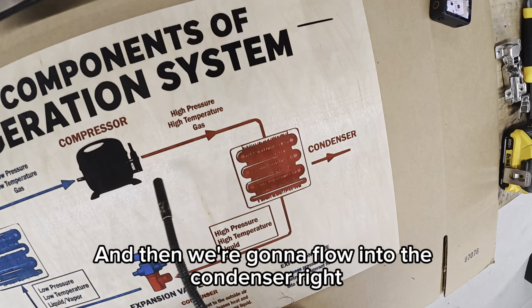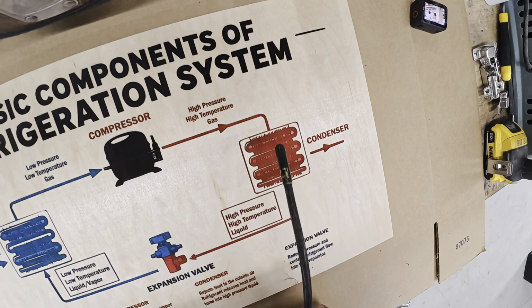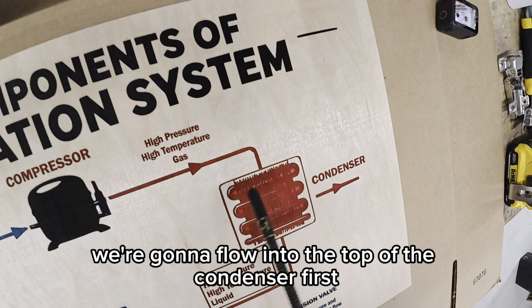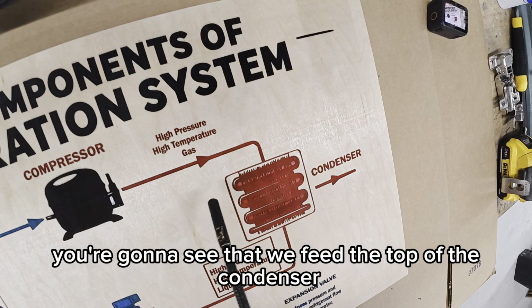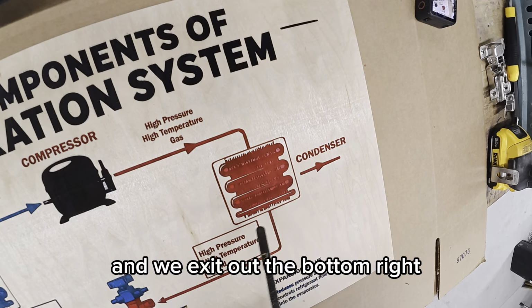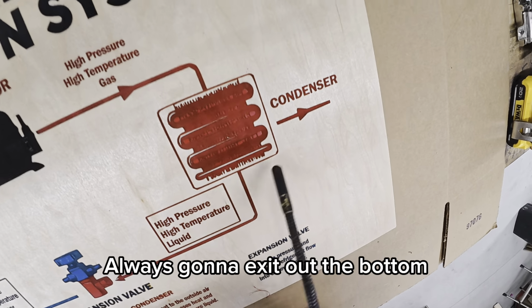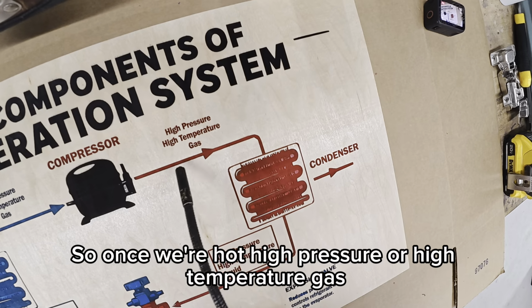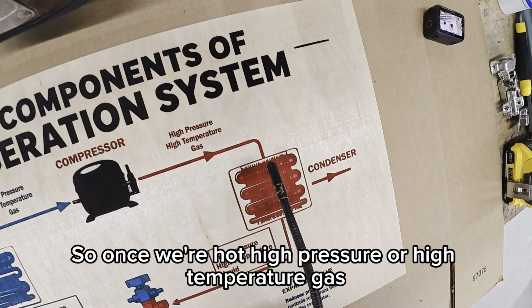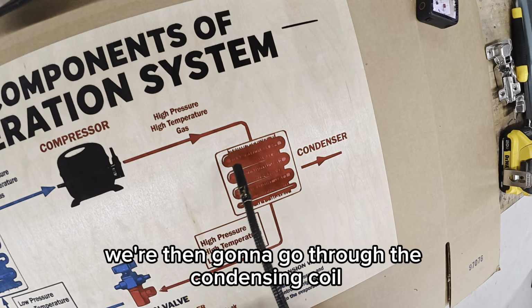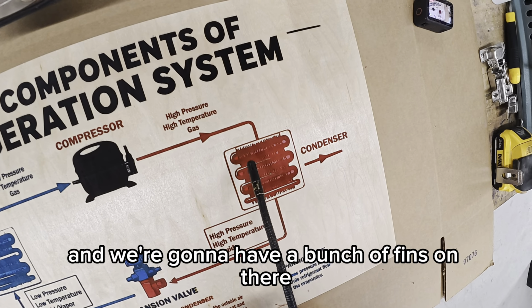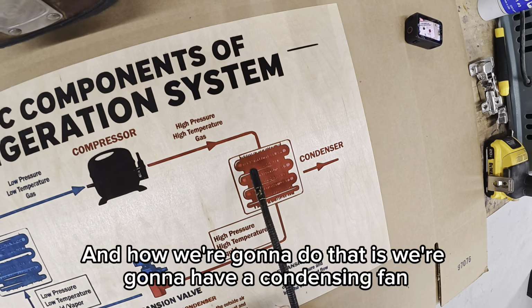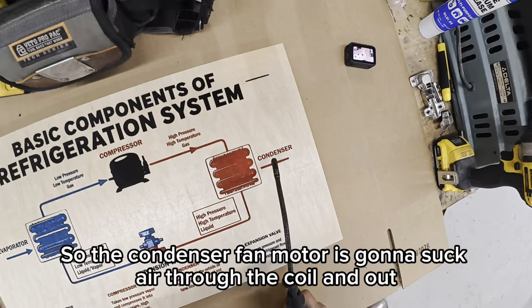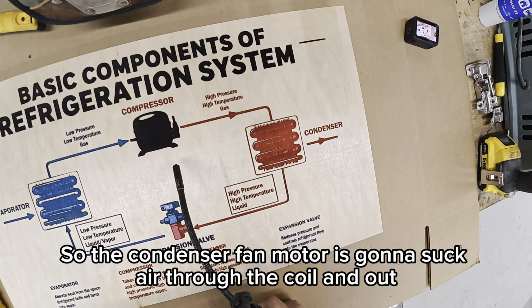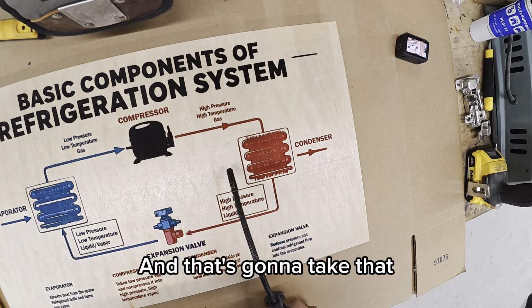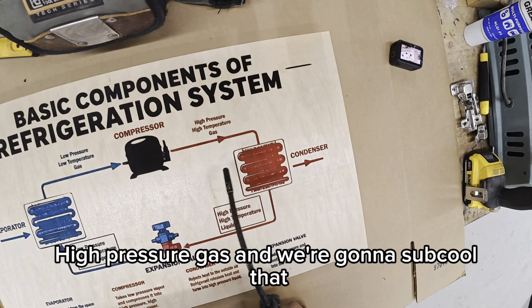Makes more sense. And then we're going to flow into the condenser, right? Always remember, guys, we're going to flow into the top of the condenser first. Almost on every system, you're going to see that we feed the top of the condenser and we exit out the bottom, right? Always going to exit out the bottom. So once we're high pressure, high temperature gas, we're then going to go through the condensing coil, and we're going to have a bunch of fins on there that's going to help us basically reject some heat. And how we're going to do that is we're going to have a condensing fan. So the condenser fan motor is going to suck air through the coil and out, and that's going to take that high pressure gas and we're going to subcool that.